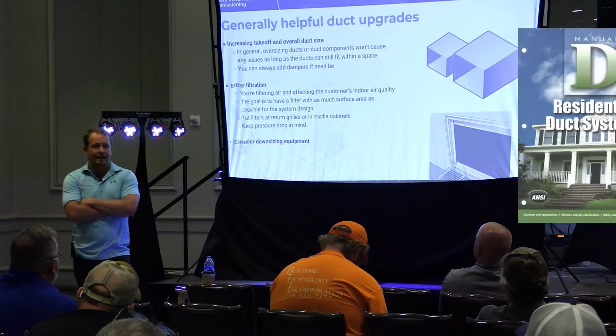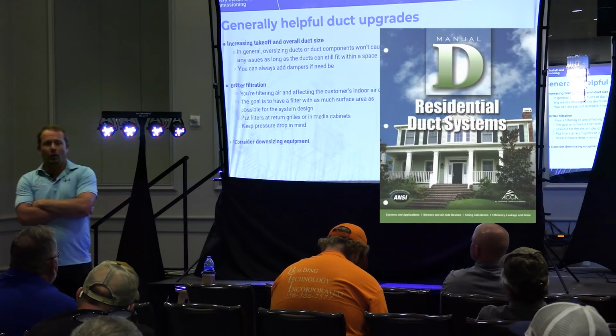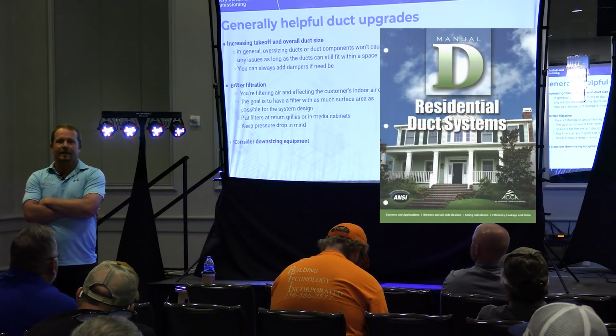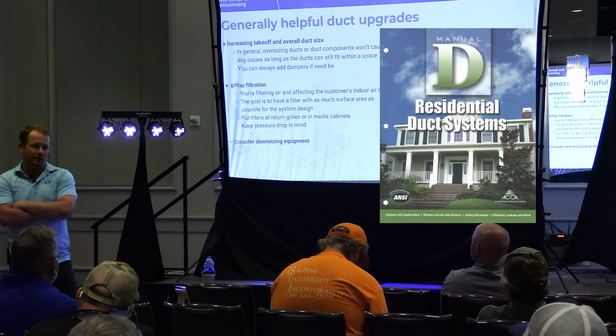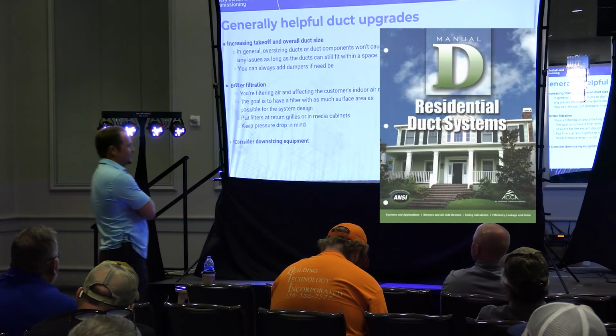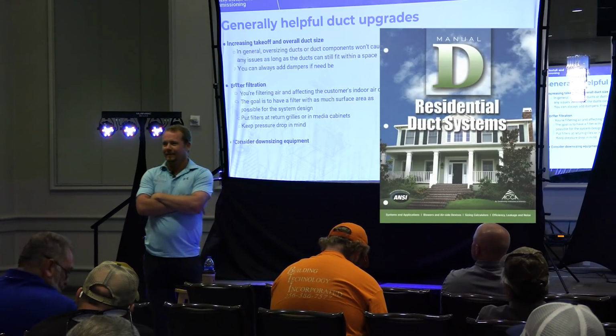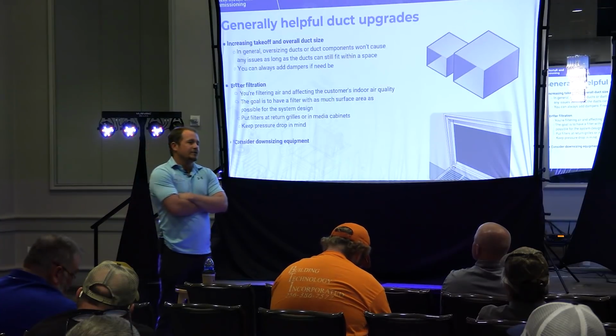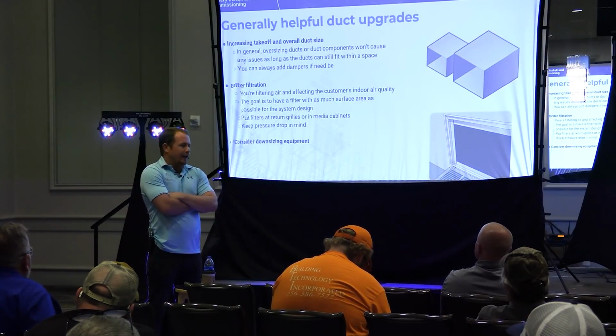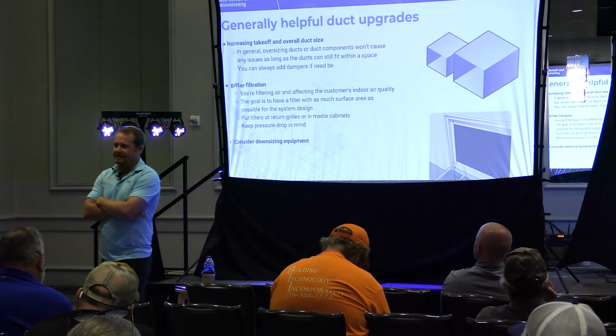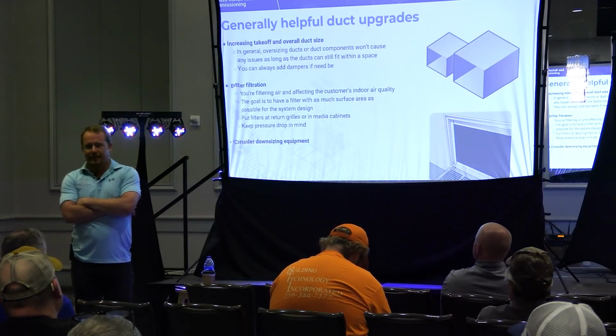In fact, if you look in ACCA Manual D, it has this little note that says, while there's some truth to the fact that velocity could cause additional gains in the ductwork, it's so negligible as to be essentially a pointless conversation or something like that. That's when it comes to trunks, make them bigger if you can. And usually we're limited by space, and so that's kind of your limiting factor.